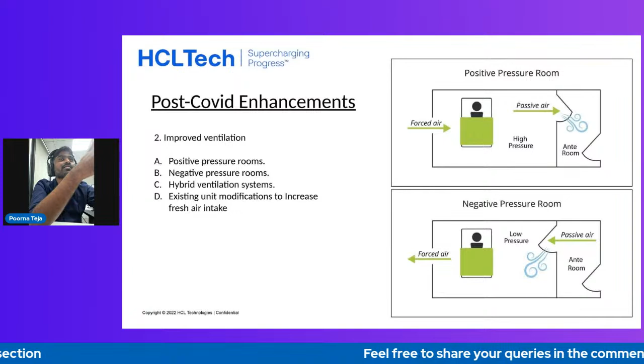Another major change in ventilation systems is increased fresh air intake. Earlier we used partial return air mixed with fresh air to dilute any pollutants inside. Now, in some cases they don't want to use return air at all, so we've changed the design to maximize fresh air intake and reduce the use of return air. Design modifications have been made in the units to achieve that.